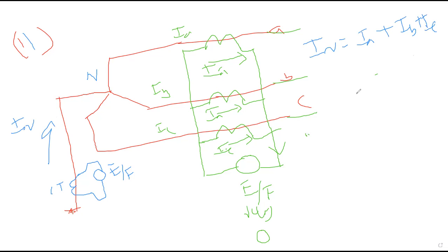Now, during no fault or healthy condition, the summation of all these currents becomes 0, right? So whenever no earth fault is involved, the neutral current will always be 0. So if the neutral current is 0, then obviously the CT is transforming no current to the earth fault relay, right? So the relay is not operating, isn't it? Are you getting my point?